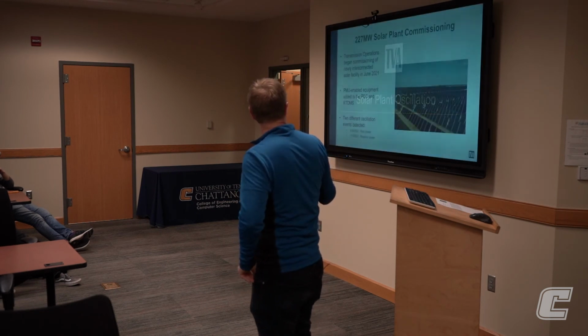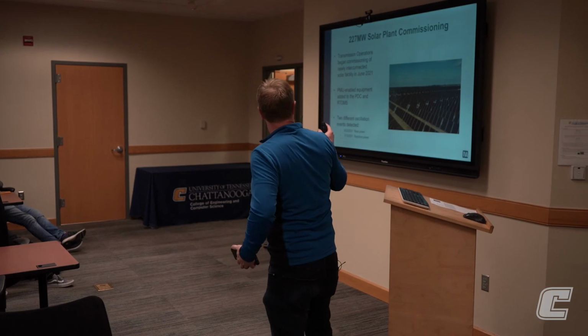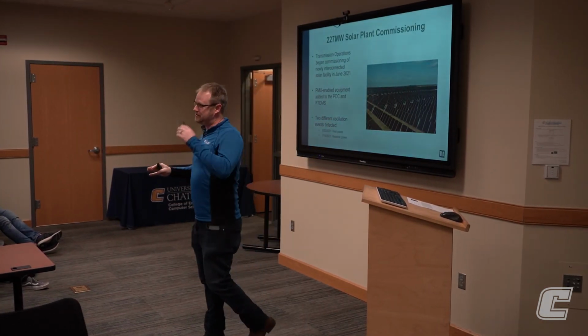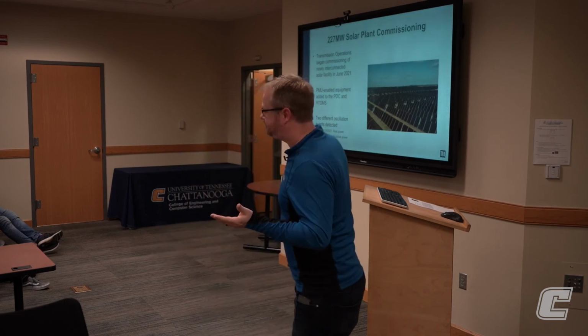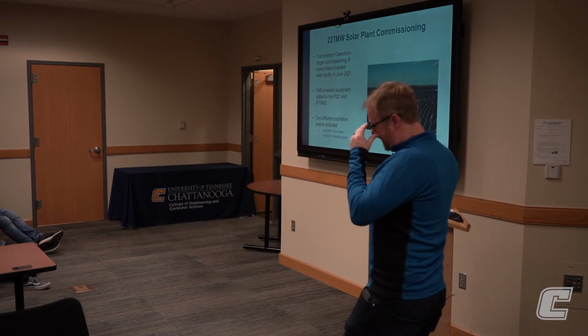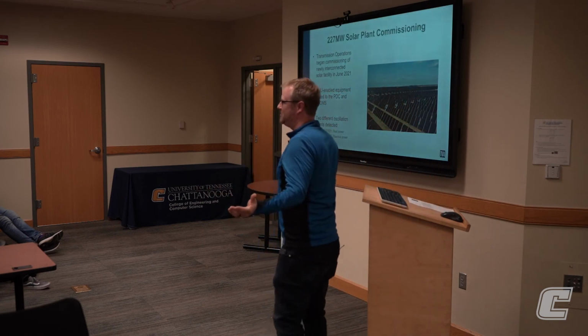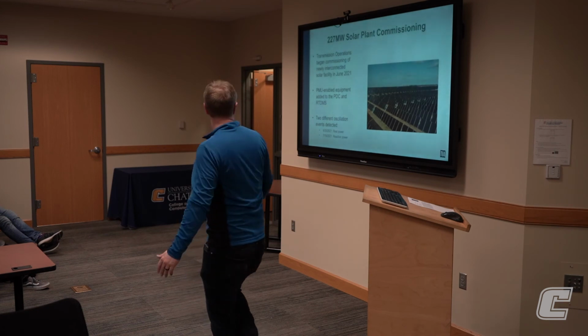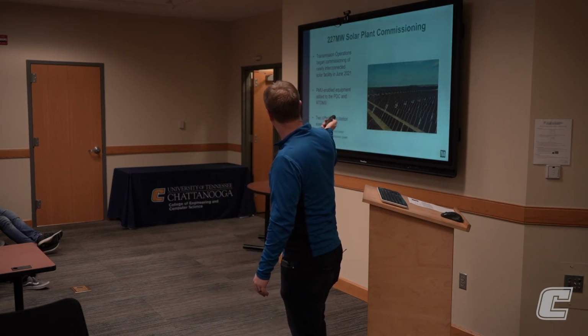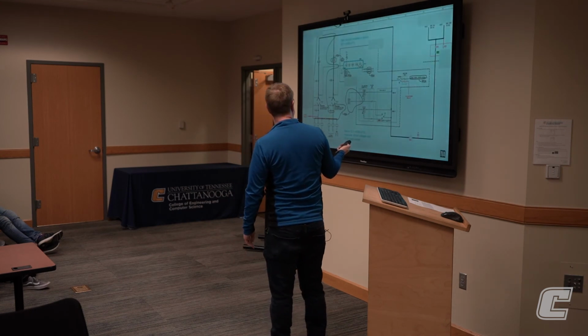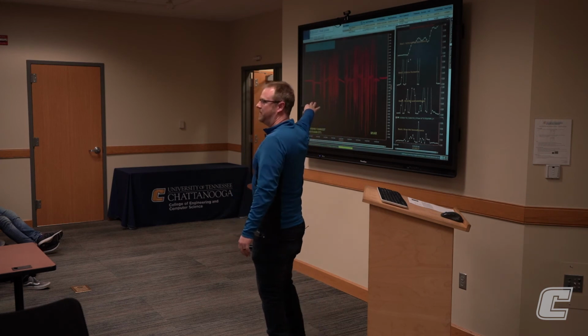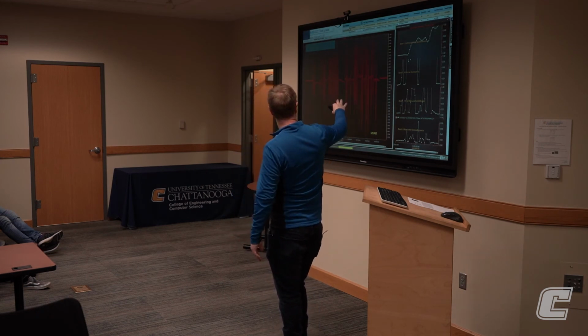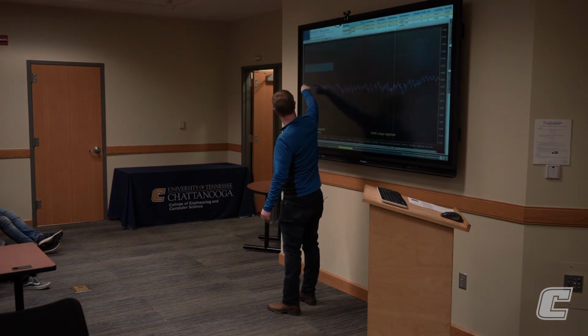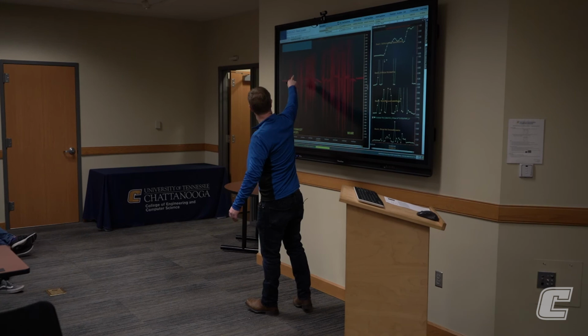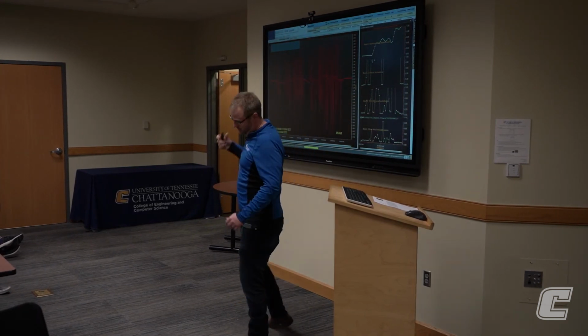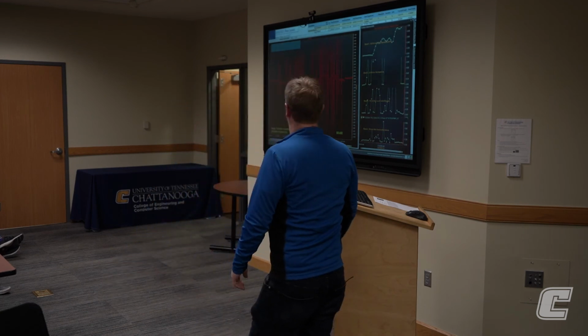Let me just touch on this. Solar, everybody talks about solar. TVA is putting in a lot of solar, and one of the problems we've had is solar oscillations, controllers on the inverters not being set up correctly. This is an oscillation we had last summer. I won't go into all the details, but this is synchrophasor data, just like we've been seeing, for the output of the plant. You can see something crazy is going on, right? It's pretty stable, then oscillates, stable, oscillates. So we knew something was wrong here, and that's the megavars.